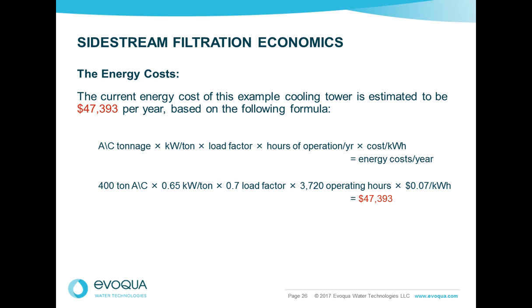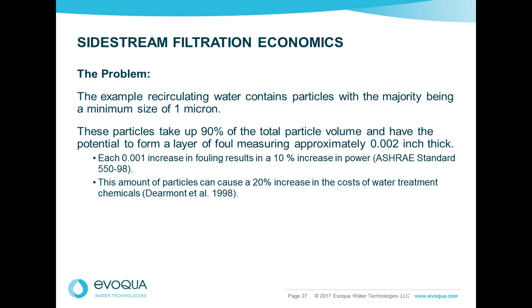So we know that energy costs can be a significant expense in a cooling system, particularly when a chiller is part of that system. And in this example, the estimated annual energy cost is a little over $47,000. That cost is calculated using this simple formula you can see on the slide. It's tonnage times the kilowatts per ton times the load times how long you're running it times your cost for electricity. It's a pretty straightforward formula you can all use to calculate your energy cost for your particular system.